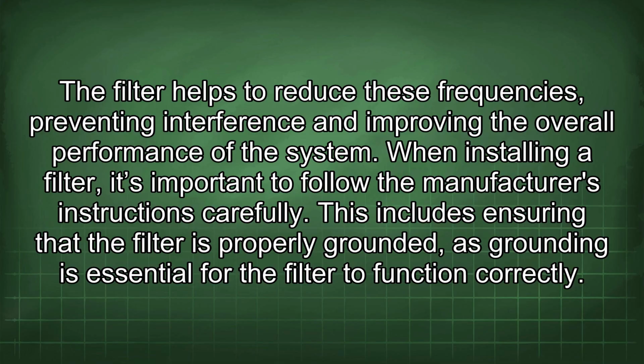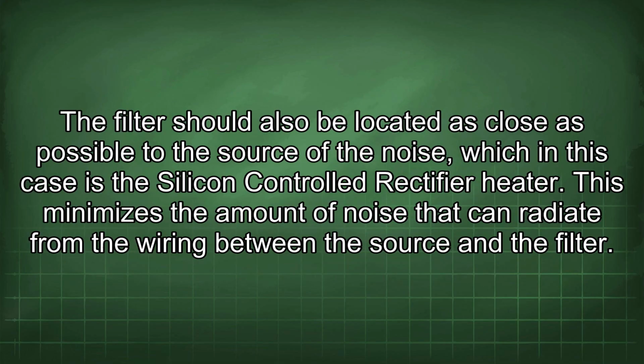This includes ensuring that the filter is properly grounded, as grounding is essential for the filter to function correctly. The filter should also be located as close as possible to the source of the noise, which in this case is the silicon-controlled rectifier heater. This minimizes the amount of noise that can radiate from the wiring between the source and the filter.